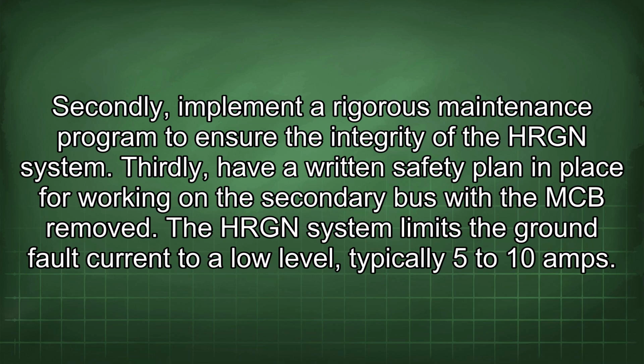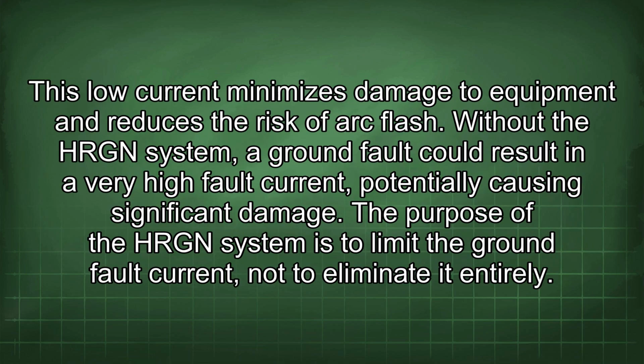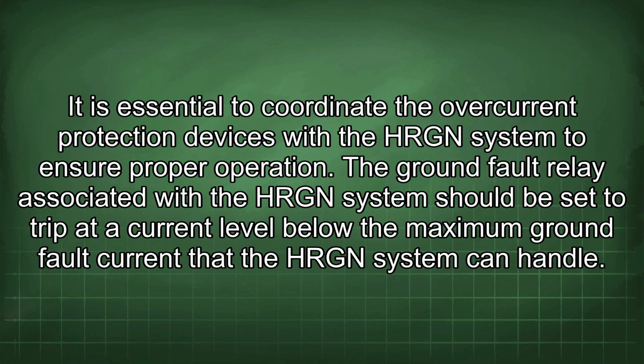The HRGN system limits the ground fault current to a low level, typically 5 to 10 amps. This low current minimizes damage to equipment and reduces the risk of arc flash. Without the HRGN system, a ground fault could result in a very high fault current, potentially causing significant damage. The purpose of the HRGN system is to limit the ground fault current, not to eliminate it entirely. It is essential to coordinate the overcurrent protection devices with the HRGN system to ensure proper operation. The ground fault relay associated with the HRGN system should be set to trip at a current level below the maximum ground fault current that the HRGN system can handle.